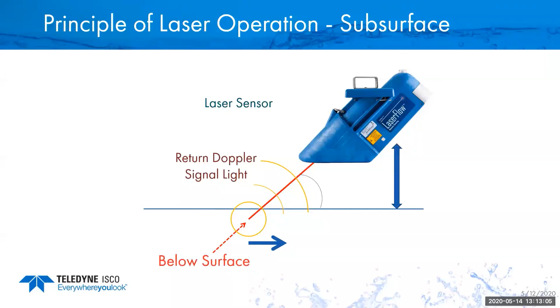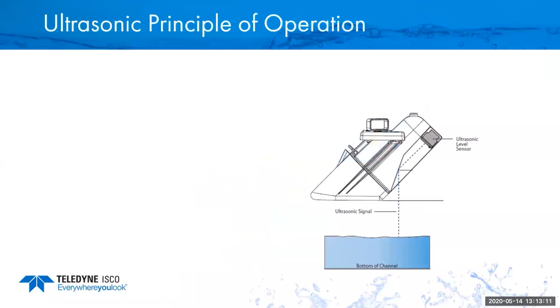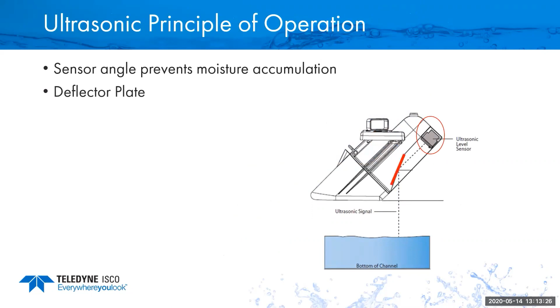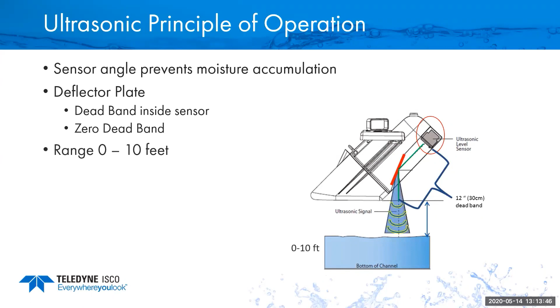And now I'm going to talk about the non-contact laser subsurface velocity technique. This has a sensor that uses an ultrasonic like the other ones, and measures the distance to the water, or the water level. Once it knows where the water is, it will focus the laser below the surface of the water. So this is one unique difference between those techniques. The ultrasonic on this design is slightly different. It's mounted at an angle up into the sensor itself, and that's intended to prevent moisture from accumulating on the sensor face. The body has a built-in molded deflector plate, which will reflect that signal off of it and hit the water surface. The beauty of that is that it is a pretty much zero deadband design. So water will now go all the way up to, including submerging that laser sensor, before it will not read. And most of these have about anywhere from 0 to 10-foot range.